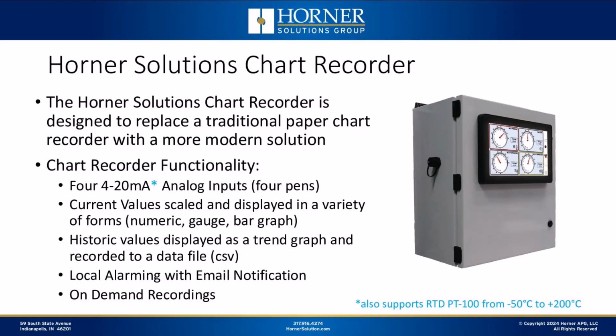It provides local alarm capability. So if you want to not only monitor a specific signal or a group of signals, and you want to have a range of acceptable values configured into this device and have it alarm when the value is outside of that range, that can be done. And that alarming can be shown locally, and it can also result in an email notification of a disruption to the process, for instance. And you can also use it for doing on-demand type recording.